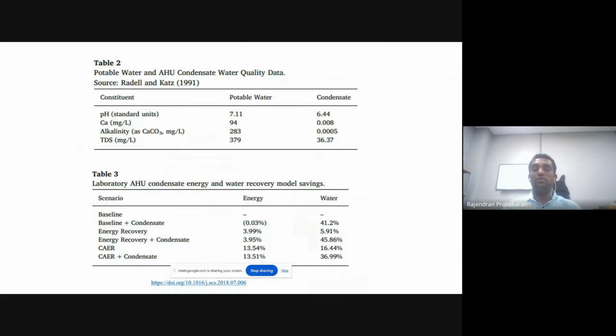And you can see there are four different categories. In the first case, baseline and only condensate, it can save 41% of water resources. And with energy recovery, after the pre-cooling purpose, you can reduce 4%. Then both energy recovery and condensate. And the last one is condensate, pre-cooling and energy recovery. Overall, you can see that the total energy of the system is reduced significantly by 13%, and you can also use the same water in the cooling tower. It will save water resources by 37%. So it is clearly visible that using condensate water can enhance the performance and also reduce the external water sources.